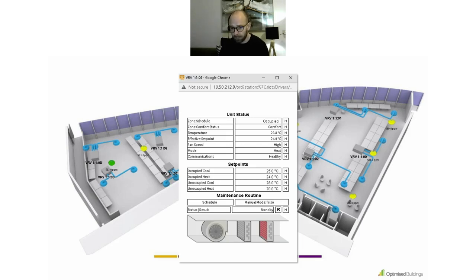In this particular space, we just have return air sensors on the VRVs, but you'll be aware that a lot of VRV, VRF systems have typically a local user interface with a small display that displays the temperature set point. So we provide in the application some future proofing that enables the user to offset this temperature. That's why we've got an effective set point there.